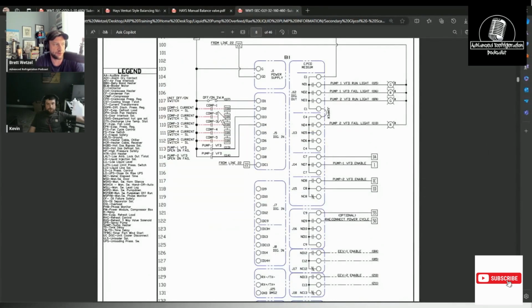So you have a current switch, and that's essentially your enable, right? So if not at least one of those compressors is on - because of the way it's wired, they're all wired in parallel - if you don't have at least one compressor going, it should disable the whole kit and caboodle.